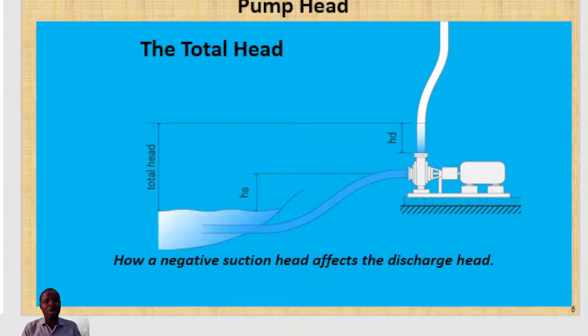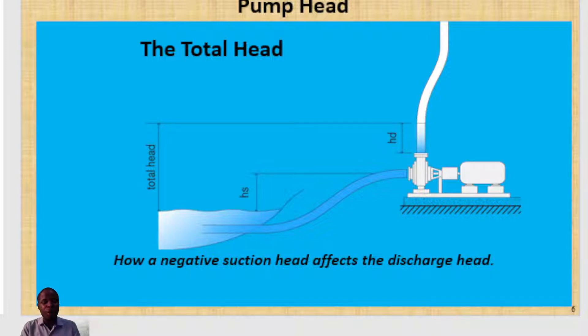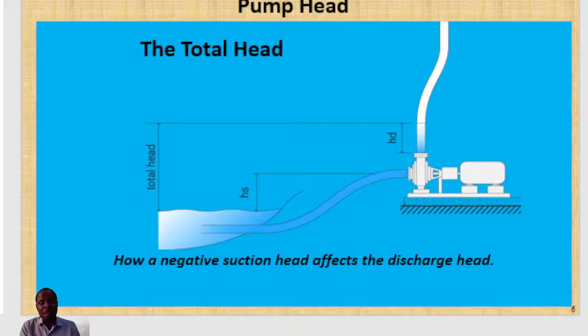We also have another concept, which is a negative suction head system, where you have your pump suction tank below the pump centerline. Imagine you are drawing liquid from a tank where the level of the liquid is below the pump centerline — referred to as negative suction head. The pump will still produce the same total head, but the discharge head at the discharge line, referred to as HD, will definitely go down.